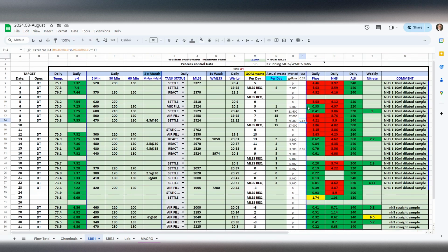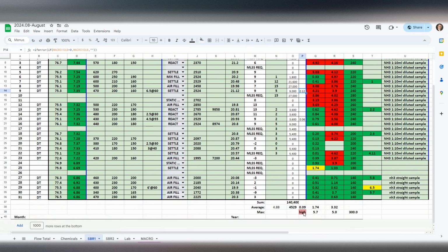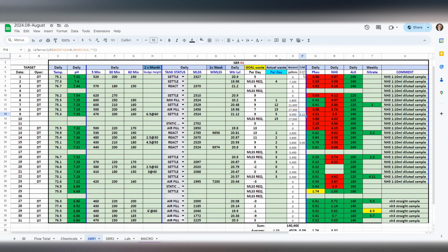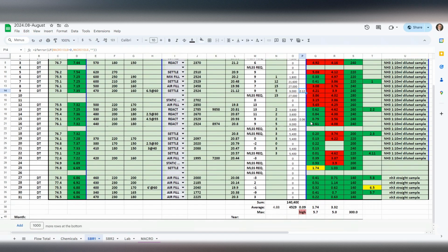to mass ratio. That food to mass ratio for this design of this plant should be 0.7, as it says right here. So as this number starts to creep up or down, it's actually inverse. For example, if this number starts to creep down, and say we just change this to 2100, you'll see that number bounce up. So a lower food to mass ratio means you're going to need a lower mixed liquor in the tank to bounce that back up.